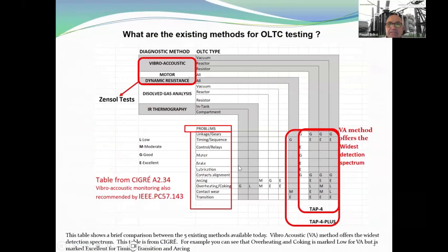What are the existing methods for OLTC testing? This table shows a brief comparison between the five existing methods available today. The vibroacoustic method offers the widest detection spectrum. This table is from CIGRE. For example, overheating and coking is marked low for vibroacoustic, but timing, transition, and arcing are marked excellent. All problems — linkage, timing, control, motor, brake, lubrication, contact alignment, arcing, overheating, contact wear, and transition — are rated. Vibroacoustic, motor, and dynamic resistance tests are all done by Zensol Tests, along with dissolved gas analysis and thermography.